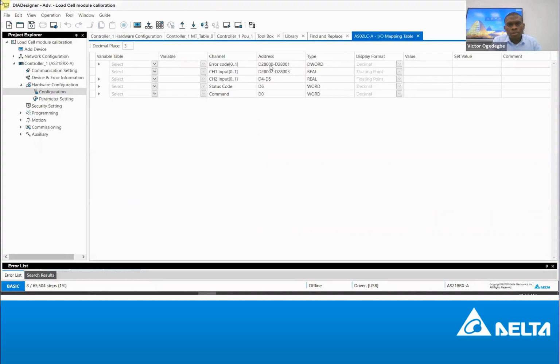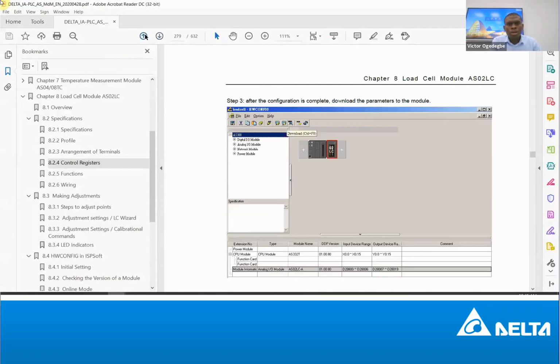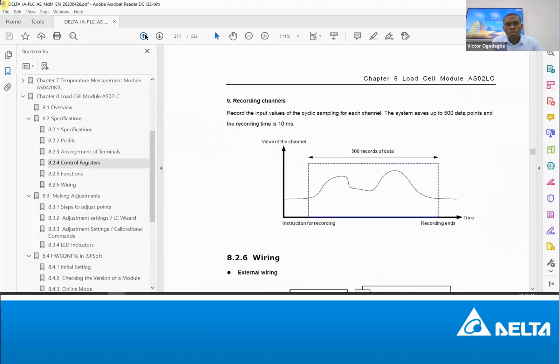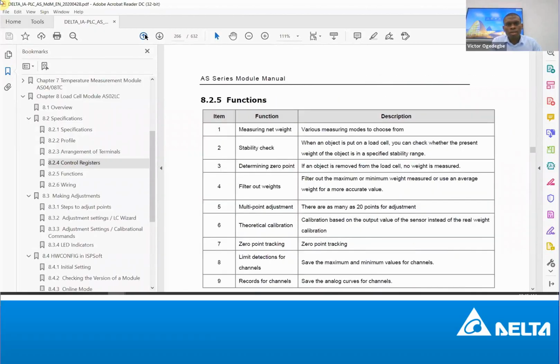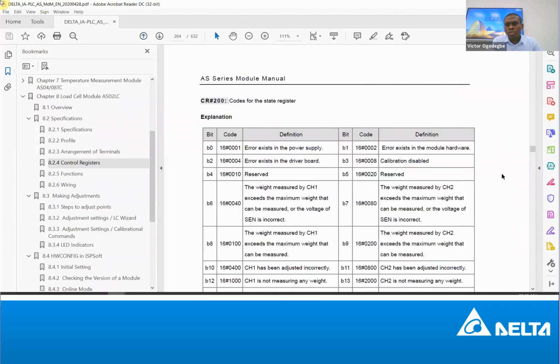The first one is the error code, a double word. And then you see the inputs for channel 1 and also for channel 2. These are the addresses assigned to it. This was what I told you, the command. It's like this D0. This D0 is the command address. There are various commands you can write to it. This is what I mean. If I show you this, I think this is the manual. It's somewhere here. Yes, this is the status code. I think I showed that earlier.